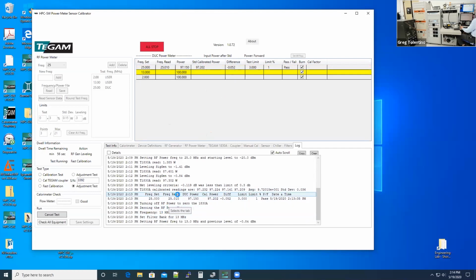The system switches to 13 megahertz. Among other things that it did, as soon as it set the generator to 13 megahertz, it chose a new path through the low-pass filter system. We'll talk a little bit about this filter bank while the system's leveling. In each one of these chassis, there are 8 sets of low-pass filters that cover 3/4 of an octave. They have a very steep roll-off above their breakpoint, so we're effectively filtering out at least second through 7th harmonic with at least 30 dB of cut.